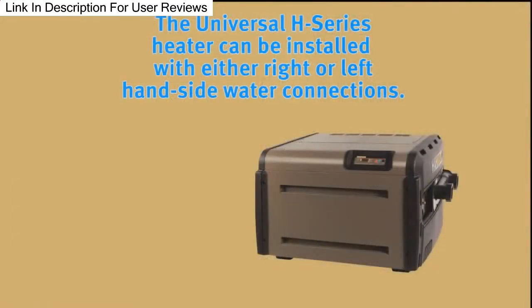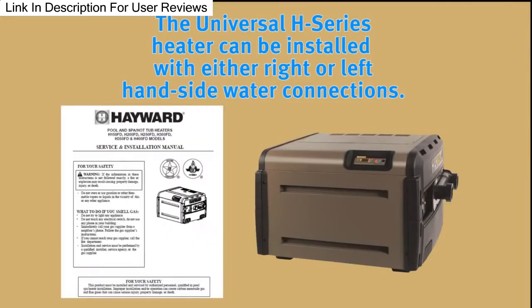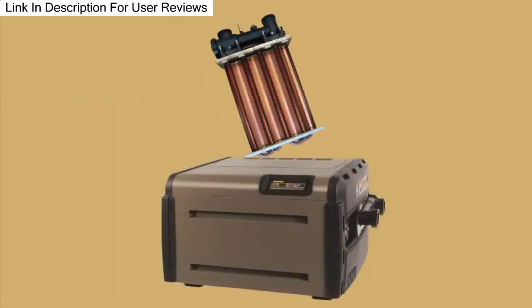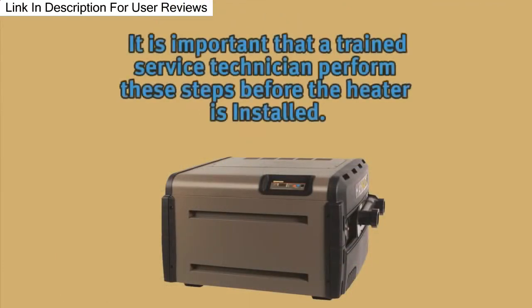The Universal H Series gas heater is designed so that it can be installed with the water connections located on either the right or left-hand side. Heaters are factory shipped with right side water connections. To move the connections to the left side, follow the instructions found in the installation manual. Remember to rotate the heat exchanger, don't flip it. A trained service technician should perform these steps before the heater is installed.